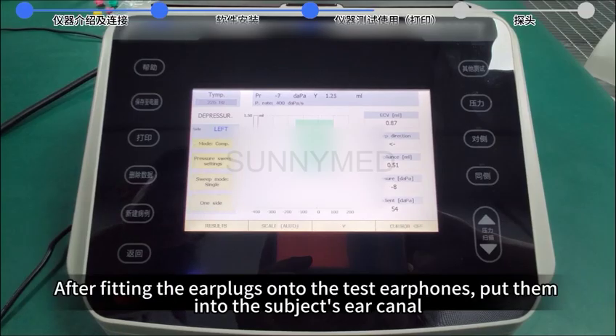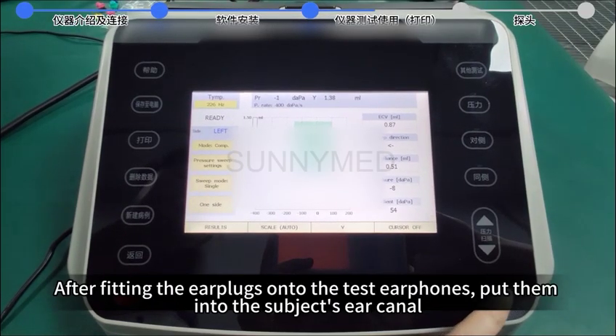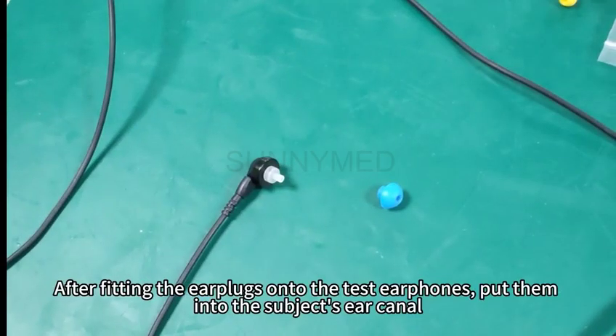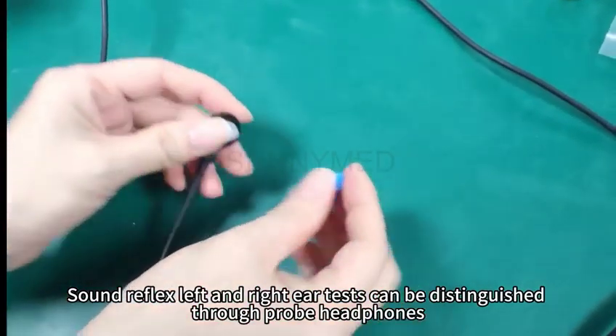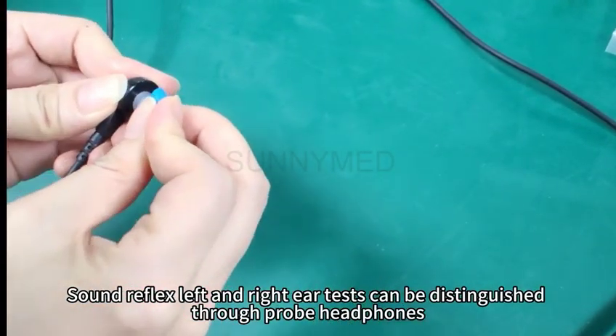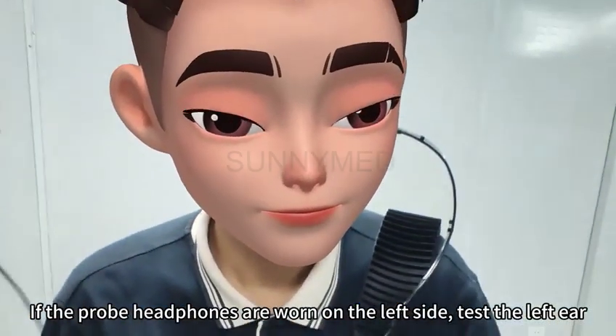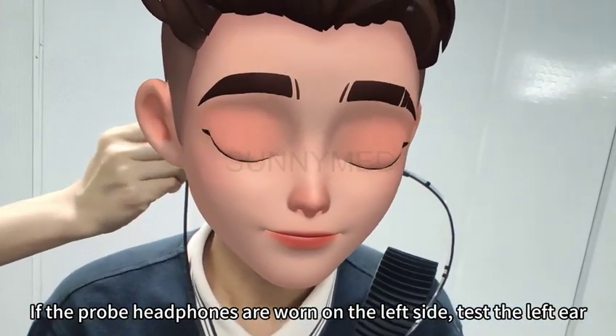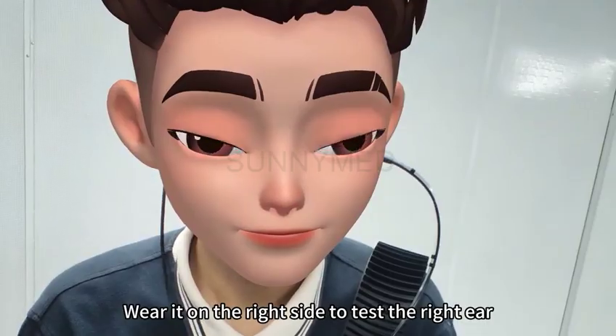After fitting the earplugs onto the test earphones, put them into the subject's ear canal. Sound reflex left and right ear tests can be distinguished through the probe headphones. If the probe headphones are worn on the left side, test the left ear. Wear it on the right side to test the right ear.